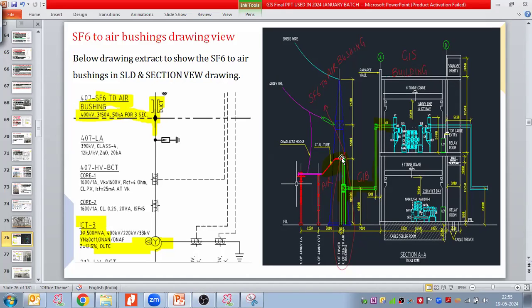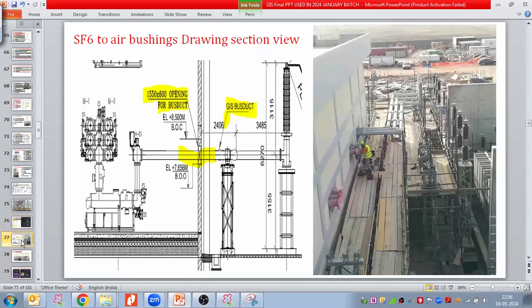Now, in order to terminate the overhead transmission line, which is connecting to the surge arrestor and the CVT, it is terminating to the gas to air bushing. So one side of the gas to air bushing is connected to the conductor, and the other side of the gas to air bushing is connected through the gas bus duct to the gas insulated switchgear. Am I clear with the terminations? Let us see a few more drawings for the terminations.